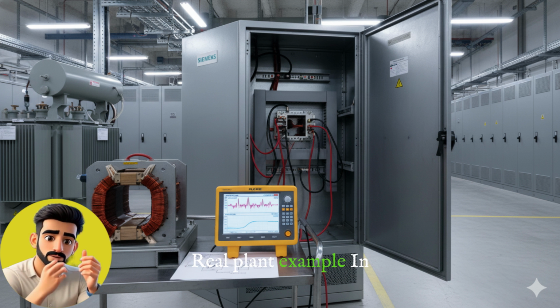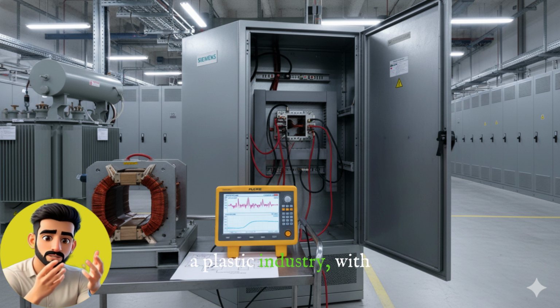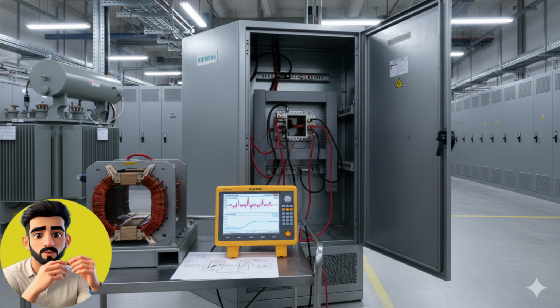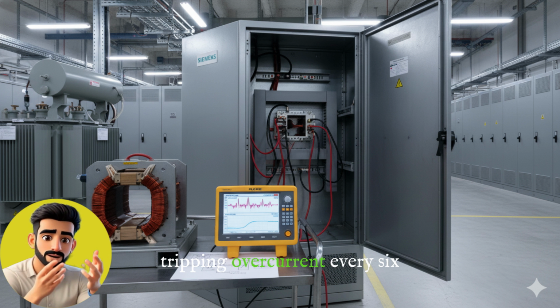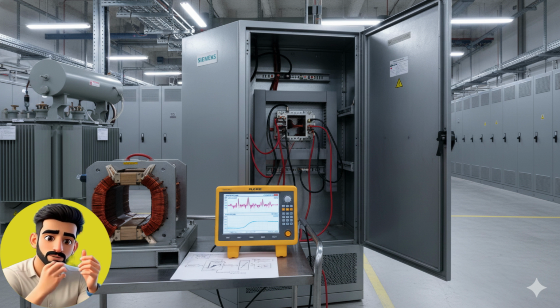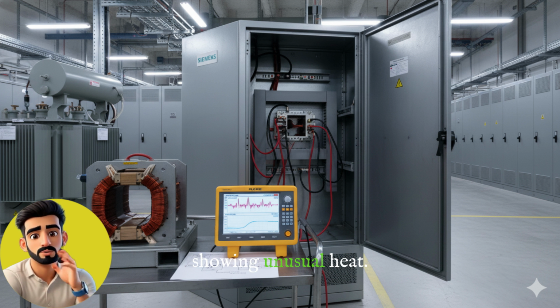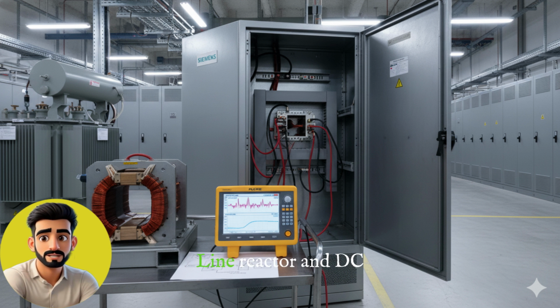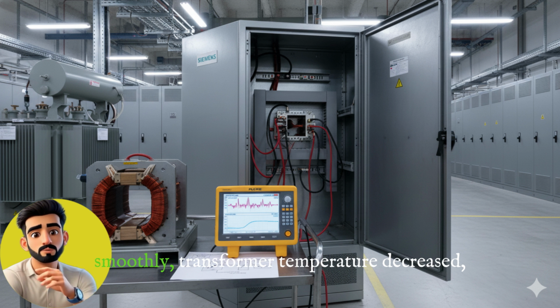Real plant example. In a plastic industry with a 100 kilowatt VSD, all the drives were tripping overcurrent every 6 to 7 days. The transformer was also showing unusual heat. Line reactor and DC choke were installed. The difference was visible within a week. The drive started running smoothly.